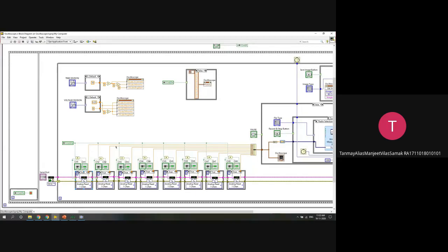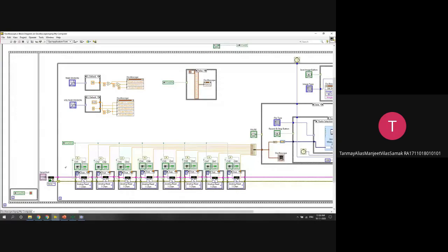Signal acquisition runs continuously, but the user can choose whether to visualize each channel. This is important because unused channels may carry noise, and having all eight visible at once could make the waveform very cluttered. Each channel control feeds directly to an indicator LED showing which channel is active. For each channel, there is a case structure: if the channel is on, the data for that channel is demultiplexed and passed forward; if off, a constant value of minus one is returned.